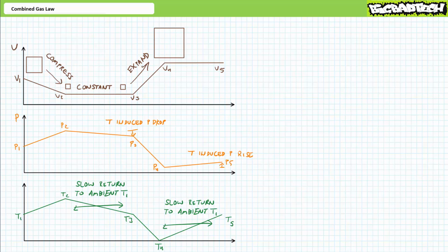Accumulators can be used to augment fluid flow, suppress shocks, control noise, or act as an emergency source of hydraulic power, among other applications. Rapid adiabatic charging or discharging of an accumulator ultimately results in the storage or release of slightly less hydraulic energy, whereas slower isothermal charging or discharging of an accumulator results in the storage or release of slightly more usable hydraulic energy. It's for this reason accumulator charging and discharging occurs at a slow rate, and sizing an accumulator for a hydraulic system must take these nonlinearities into account.